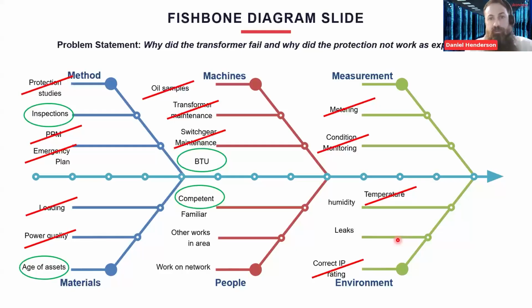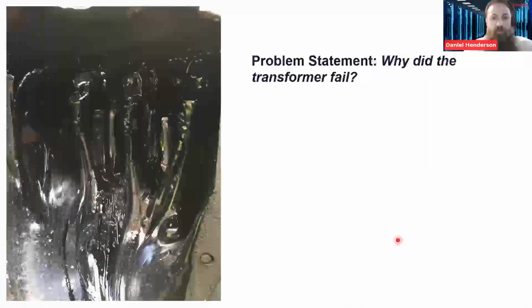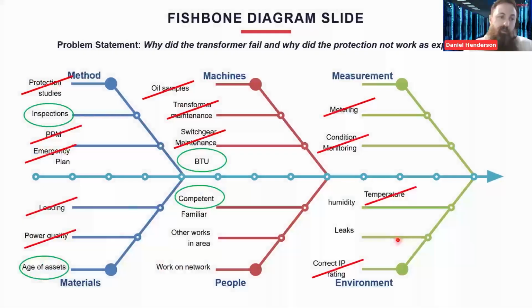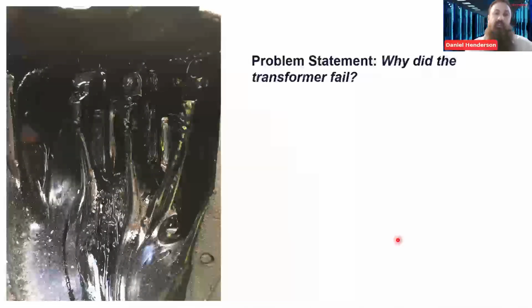So I guess at this point we've got to a point here of why the transformer failed. We've got a couple of things that are left on, and we've probably ruled out quite a few there. So what I've done is I've got in touch with a vendor who will do survey work and forensic investigations on electrical or mechanical switchgear failures. This one was switchgear specialists. So I got them to site to help determine what's gone on. Basically, I don't think we're ever going to understand why this actual transformer failed.